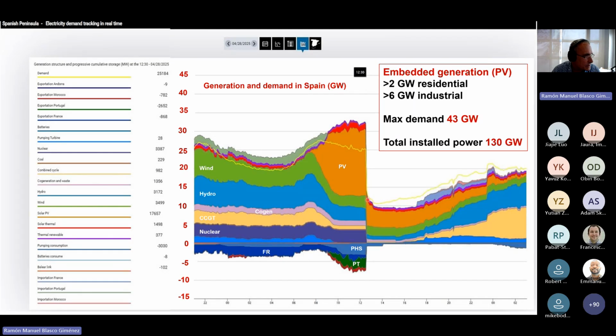What you see here was a total zero, but some SCADA system stopped sending proper data. So what you see here is that PV was still generated. No, PV was not generated, and even less at 12 o'clock at night. But you see, this wind is mainly real, this production of wind, but restoration was mainly carried out by hydro and CCGT. So those will be probably the main takings.